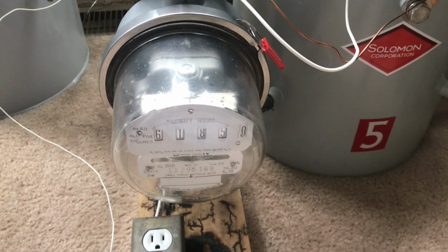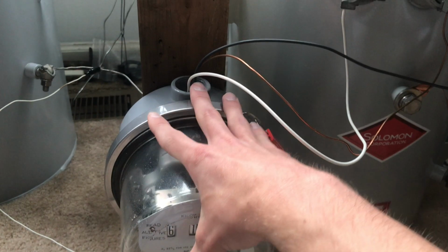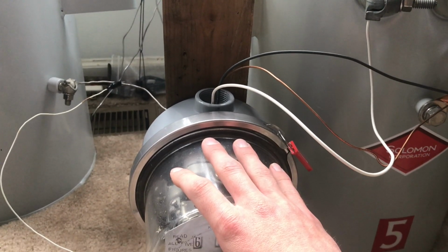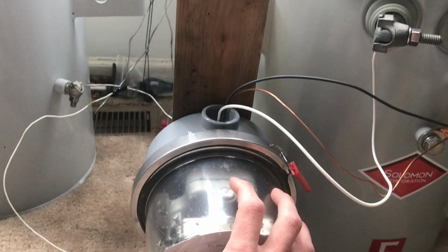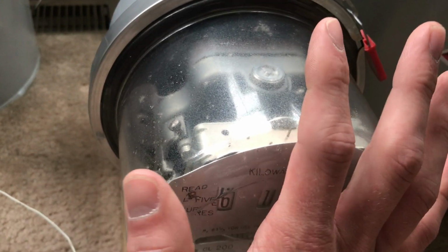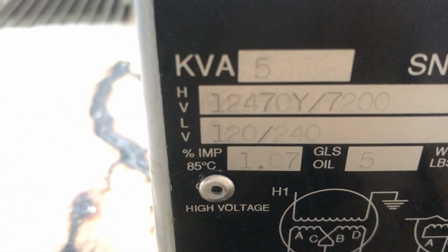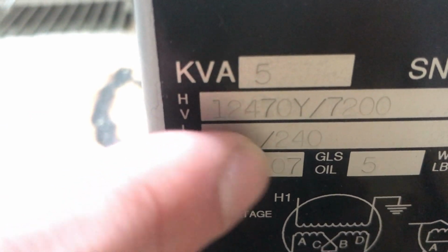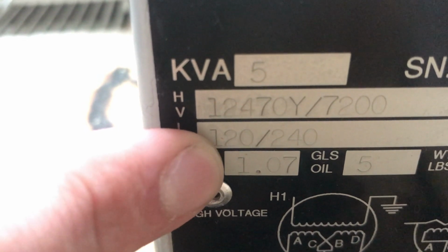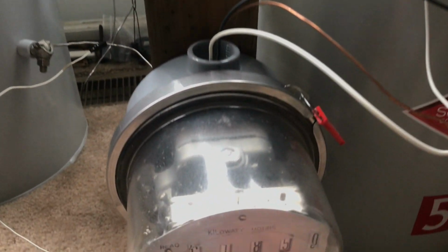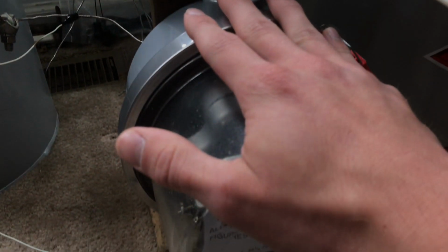Now I'm going to go inside the meter base here and just explain the voltage and how it works in a residential setting. However, this is just a demo setup, and you never want to go into your meter box or really work with anything above the main breaker. As you can see here, the reason why is this impedance right here. That is how much current this transformer will flow on a dead short. And on the low voltage side, if you were to short out these two terminals, according to that 1.07% impedance, there would be short circuit current of 1800 amps at 240 volts. And that will definitely ruin your day. So, whatever you do, leave this side to the professionals.